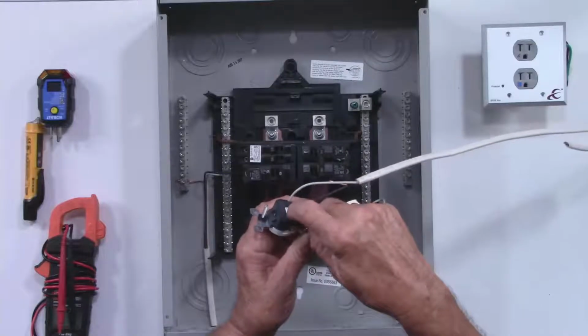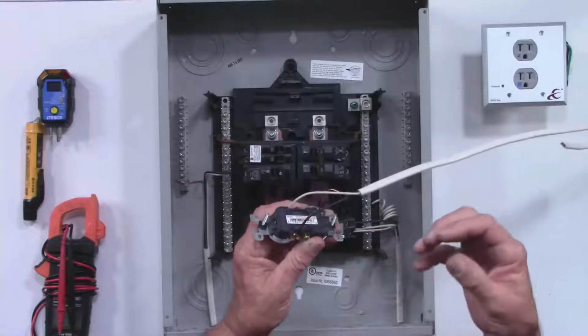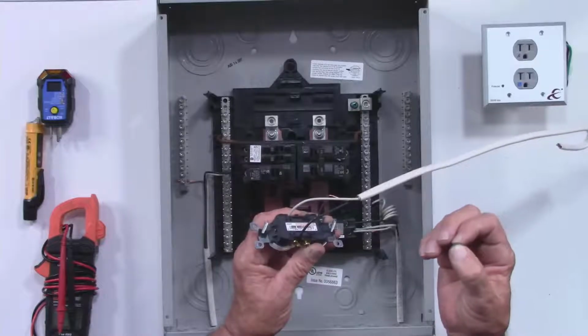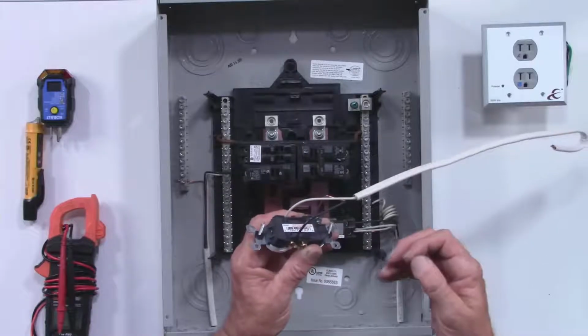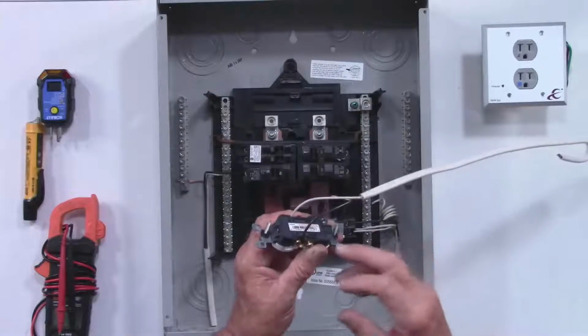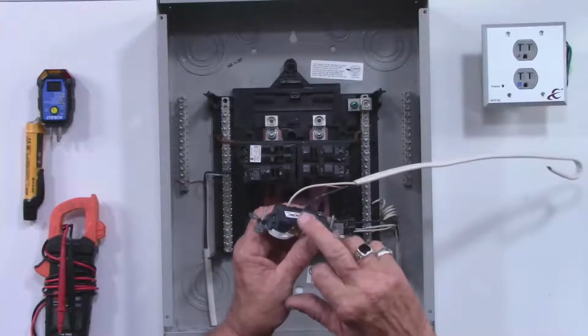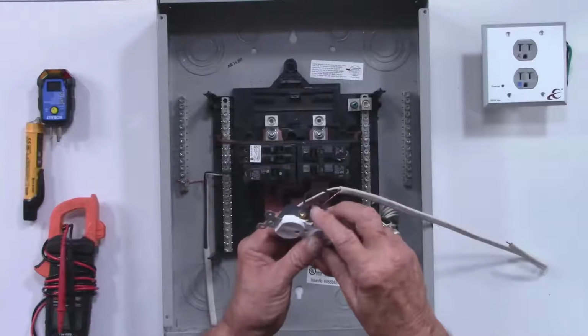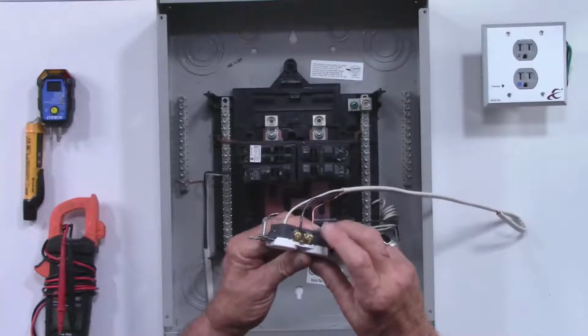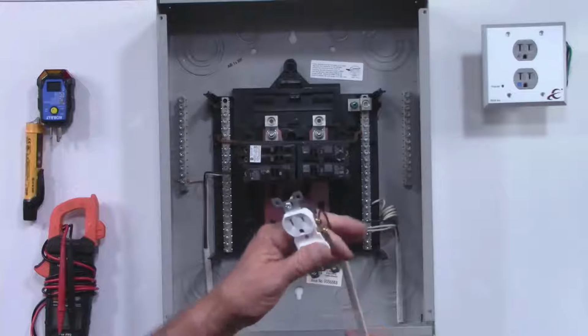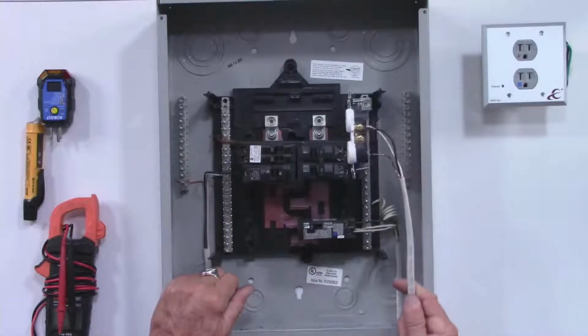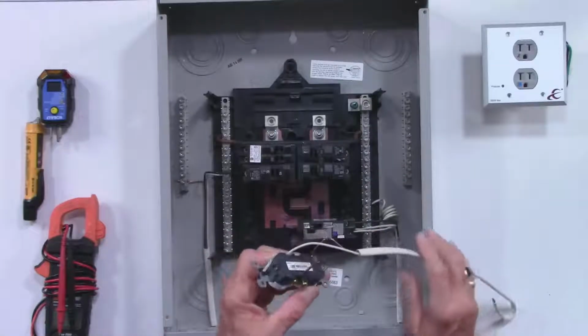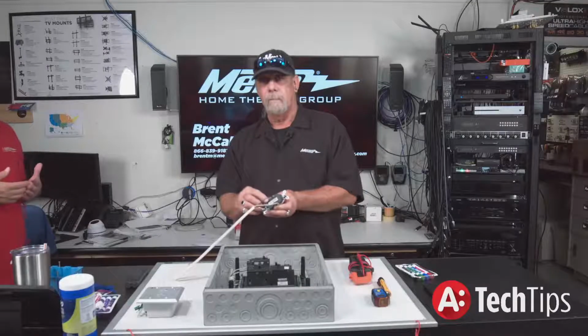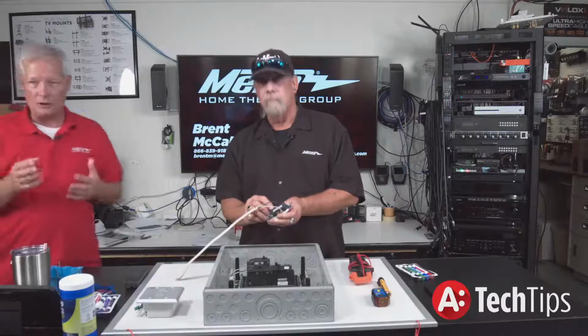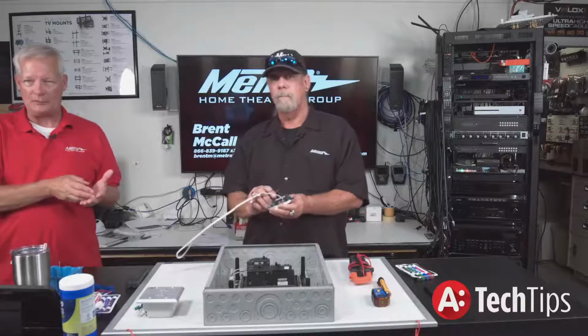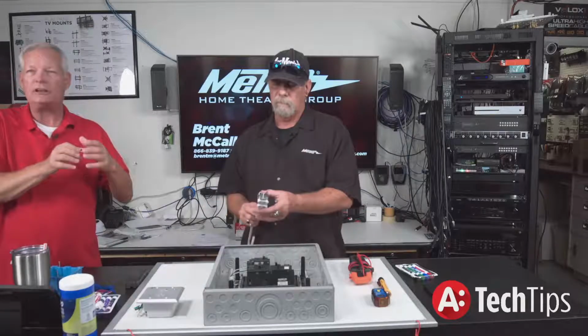I do not recommend using the quick stabs. They are a small device that just clamps on the wire. Over time and overloads, they will start to loosen up, and then you'll have a hot spot. I recommend always putting them underneath the screws and making sure you've got a good tight connection. Part of the problem with the stabs is that you have a round wire between flat blades, so you have very nominal contact with the copper. Over time, as it wears out, you can get arcing inside of them.